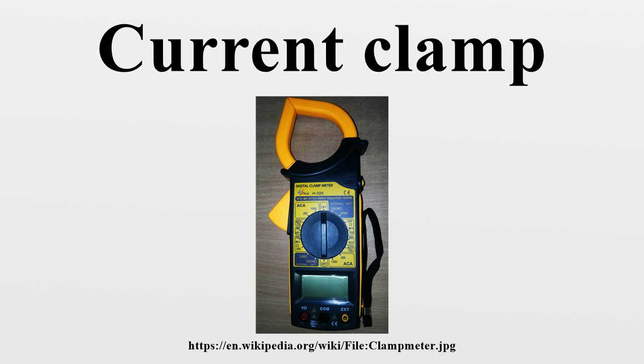Power meter, energy analyzer. Clamp probes are used with some meters to measure electrical power and energy. The clamp measures the current and other circuitry measures the voltage. The true power is the product of the instantaneous voltage and current integrated over a cycle. Comprehensive meters designed to measure many parameters of electrical energy, energy analyzers, use this principle. A single clamp is used for single-phase measurements, with an appropriate instrument with 3 clamps, measurements may be made on 3-phase power systems.